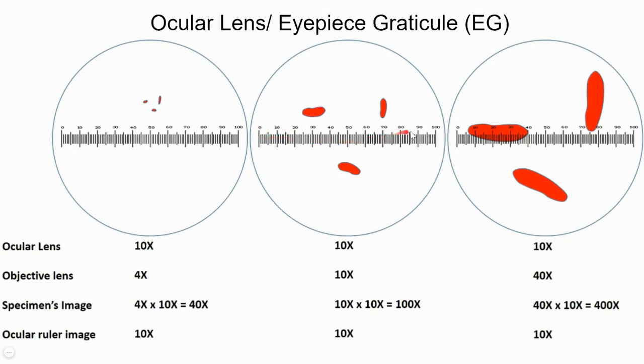In the next case, you'll notice the specimen appears larger and the eyepiece graticule scale is more clearly visible. The reason is that the eyepiece lens remains the same at 10x magnification, but the objective lens has changed from 4x to 10x — I've rotated the disc and changed the objective. The overall magnification has now become 10 × 10 = 100x, which is why the specimen looks bigger. The eyepiece graticule scale does not look different because the eyepiece lens has not changed.